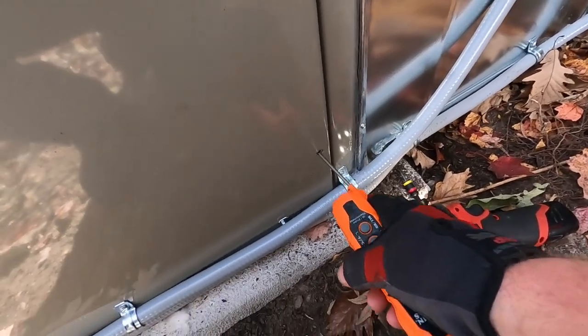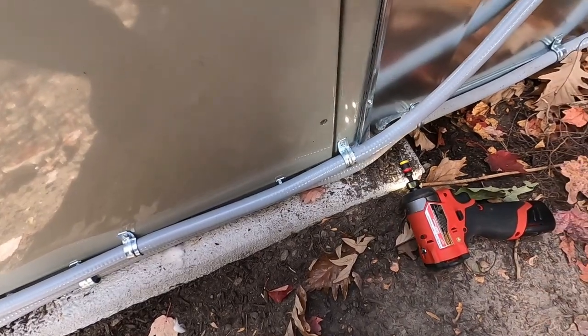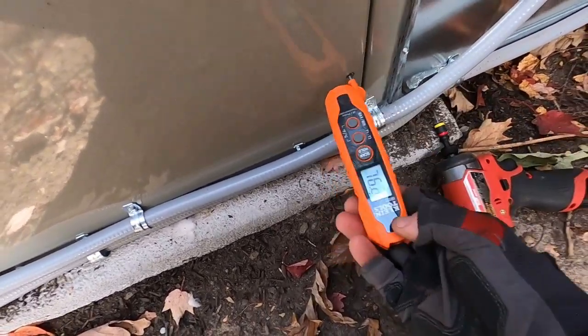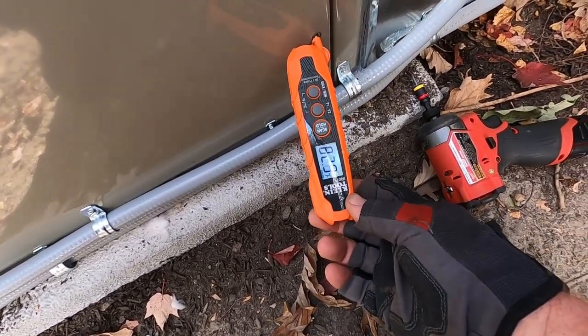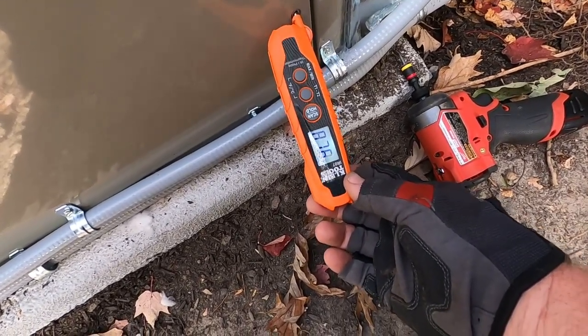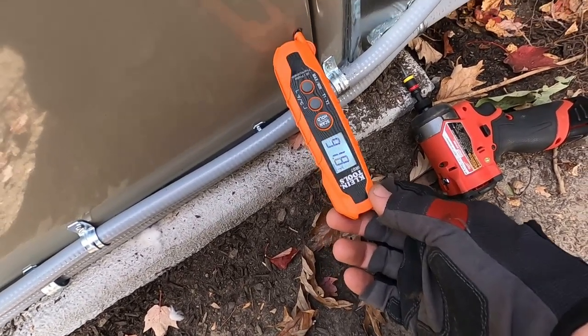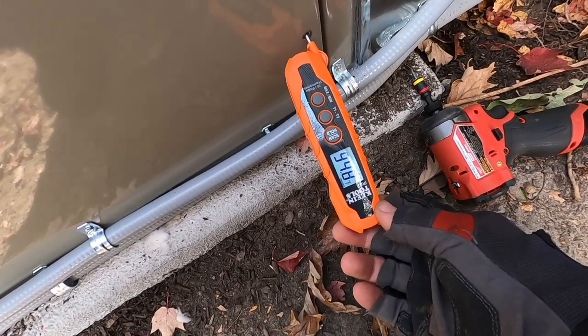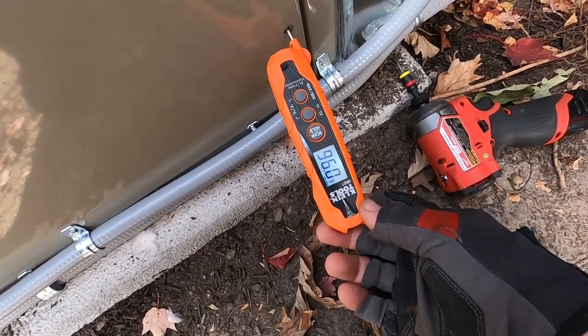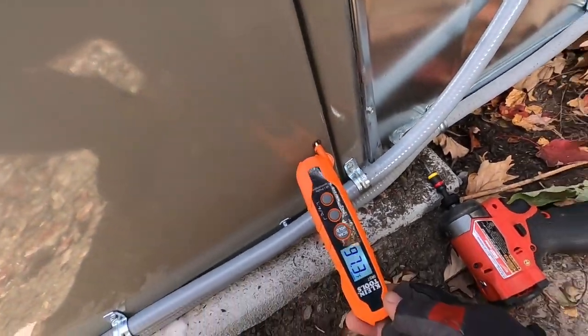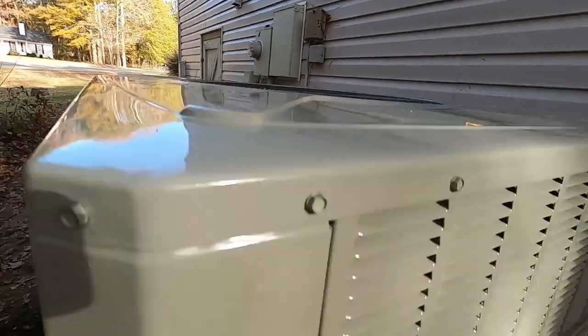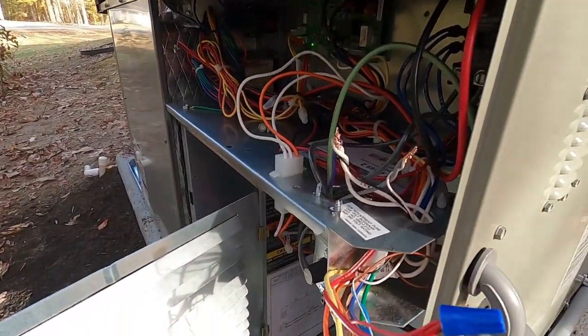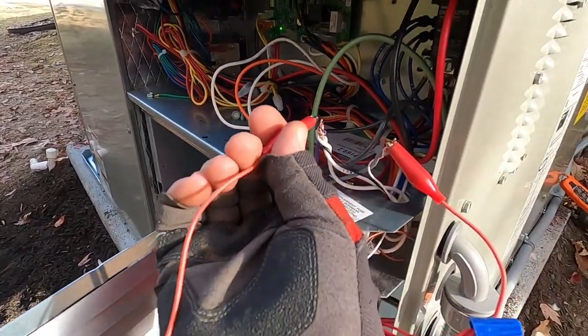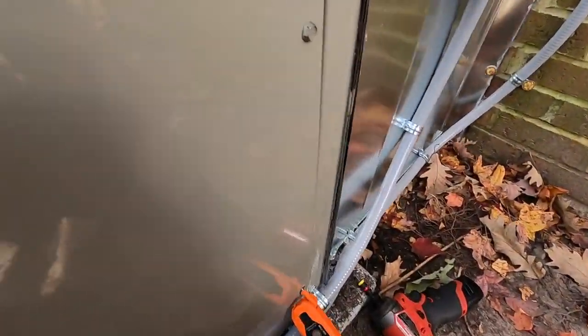We'll get a quick temp rise on the heat pump. So I'm gonna come over here real quick, see what kind of temperature I'm getting on this heat pump. Heat pump only. Reset that. And then we'll see what kind of rise we get when the heat strips activate. And that will be it. So we're getting, like I said, it's 66 degrees outside right now. So this thing is producing a lot of heat on the heat pump side. There's a lot of heat out here being absorbed in that coil. But I'm gonna go cycle these heat strips on real quick and see what our total rise of the system is with everything activated. And we should be good.